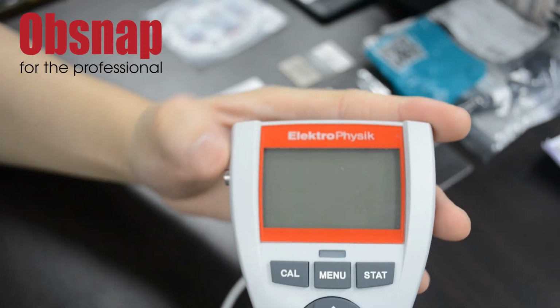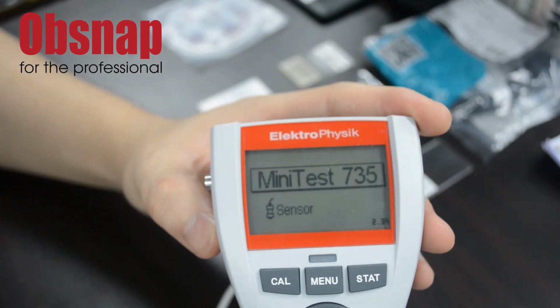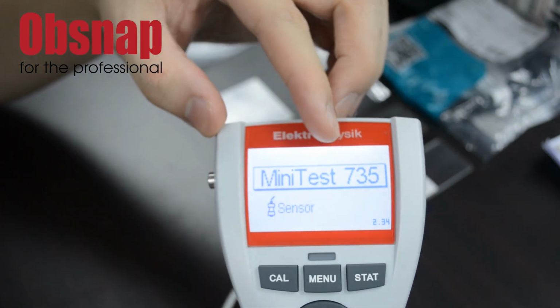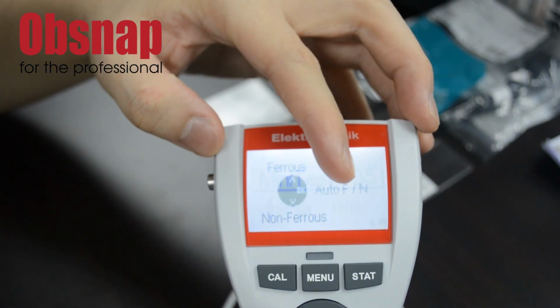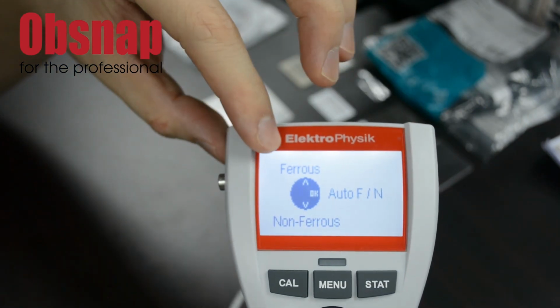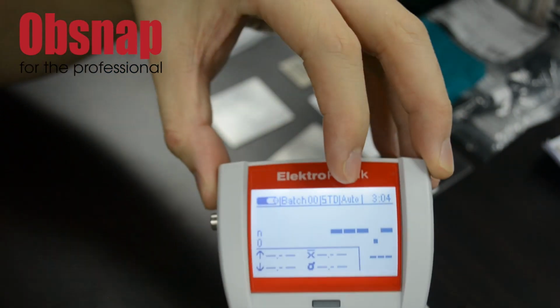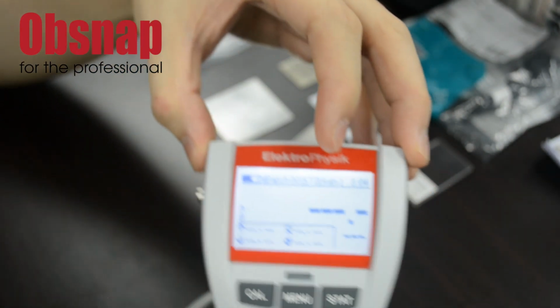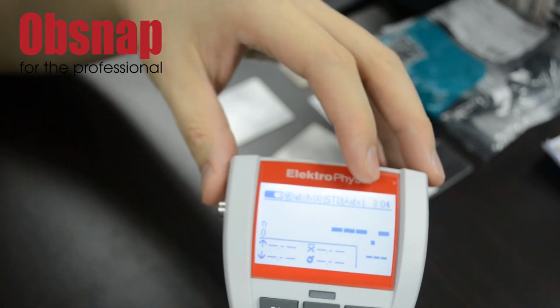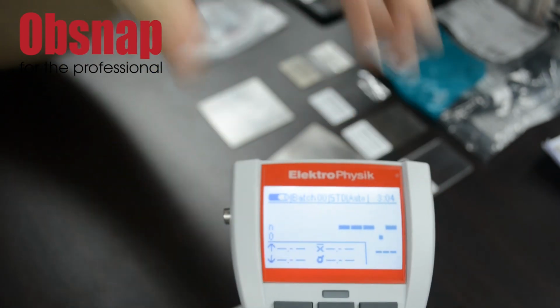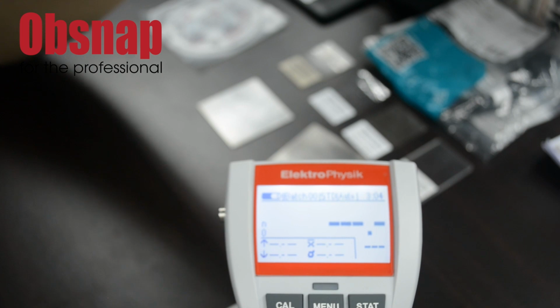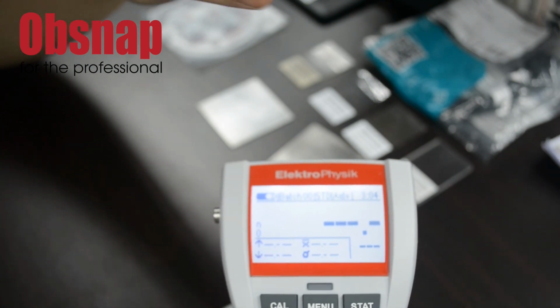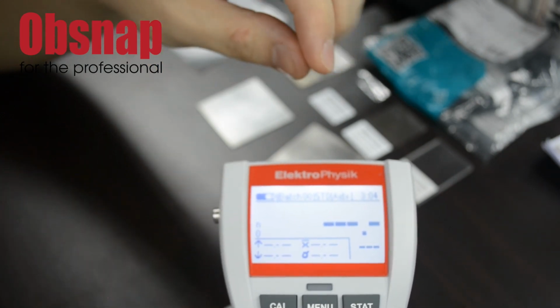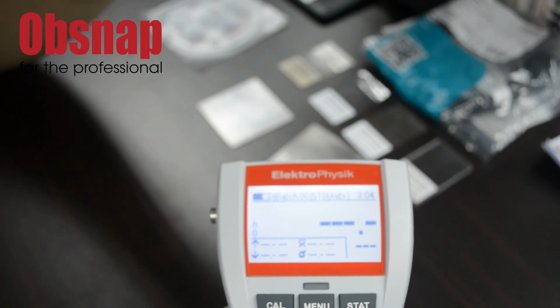Let's just turn on the unit. So we just press the on button here. You can see it's Mini-Test 735 with the FN 1.5 sensor. So it allows us to choose between ferrous and non-ferrous. So in our case, we choose auto. Ferrous means material that contains iron inside, for example, mild steel or cast iron. While non-ferrous is the material that doesn't contain any iron inside, for example, copper, bronze, aluminium.